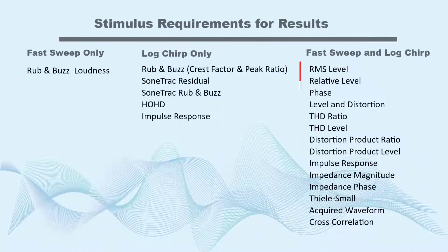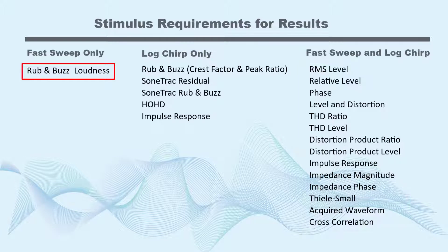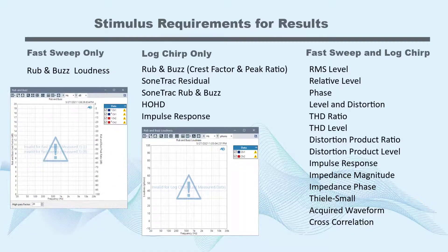While most measurement results can use either stimulus type, the rub and buzz loudness result added in version 6.1 requires the fast sweep stimulus. Additionally, a few other results require the logchirp stimulus. Result graphs indicate when the result data set is not valid for a selected stimulus.